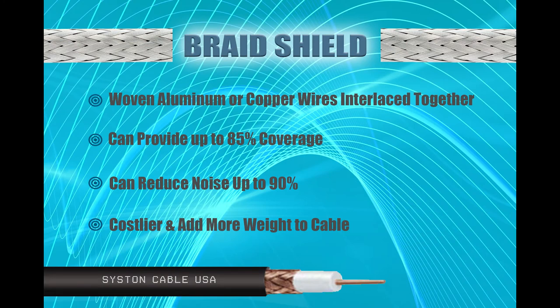Braid shielding is constructed by weaving aluminum and copper wires interlaced together. It can reduce noise up to 90%. Braid shielding can cover up to 85% of the wire, and signal noise can leak between gaps in the braided weave design. This amount of coverage should be sufficient, especially where the application does not require constant movement or flexing.